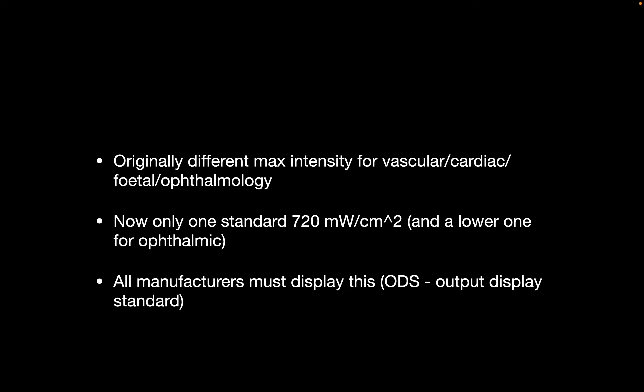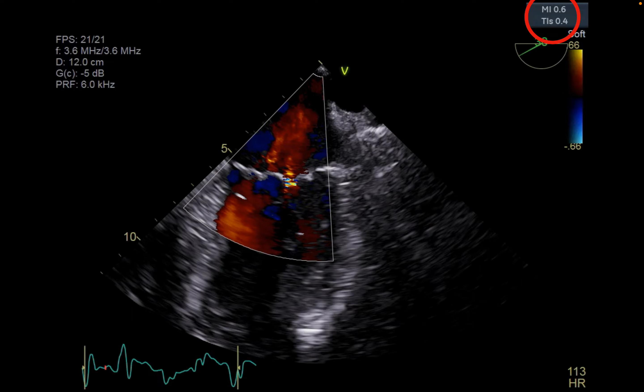And there's this ODS, which is the output display standard. It means that every single ultrasound machine will have to display on its screen how much is that TI and MI, the thermal index and the mechanical index? I will get to that in a moment. Usually it's in the corner of the image, and MI is the mechanical index, TI is the thermal index, and you really should pay attention to these numbers while you're scanning and try to use the ultrasound system so that these will not exceed recommendations.